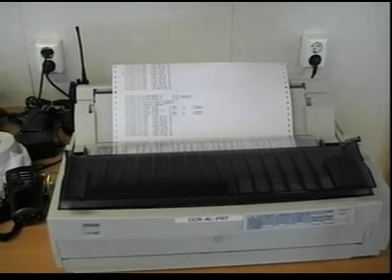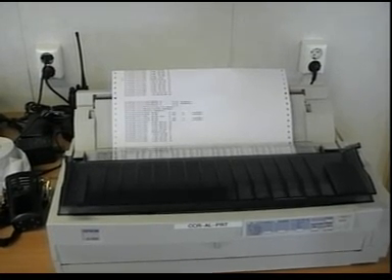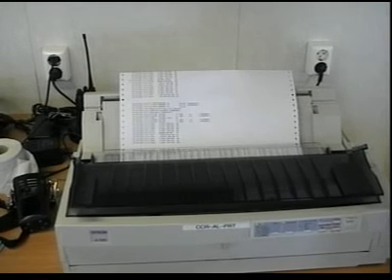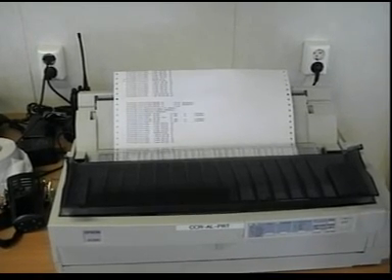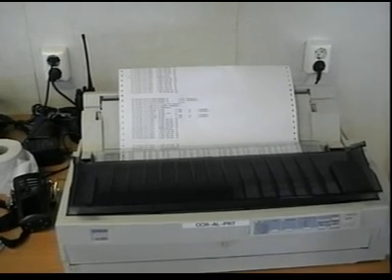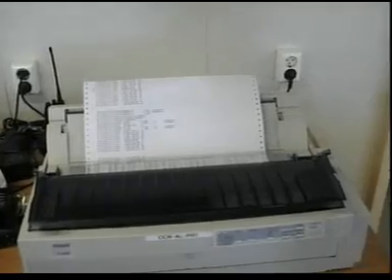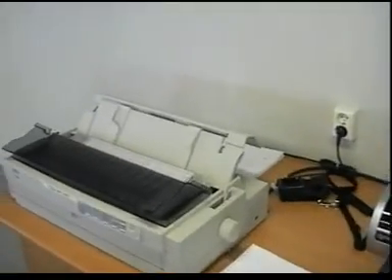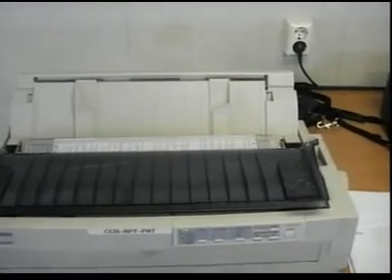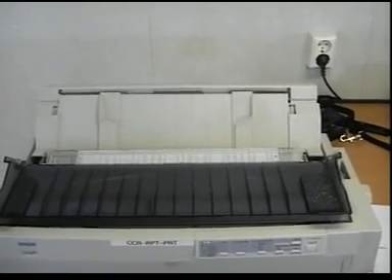to confirm what actions have been taken by any individual, whether it be a gas engineer, machinery engineer or tech officer trying to have access to the control systems, and what his action has been. There are two printers. This is the event log and this is the daily alarm log, which can be set for 12 hours or 24 hours. Normally in this ship it's set at 8 o'clock. Every day at 8 o'clock this will give us a complete status of the system.